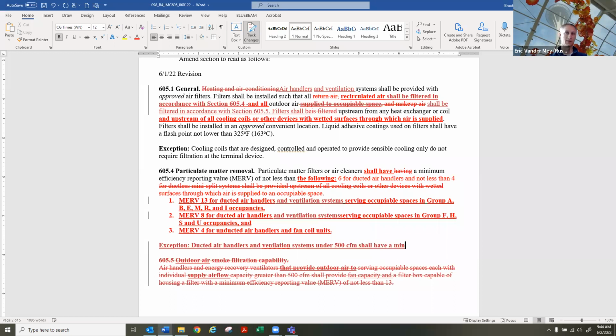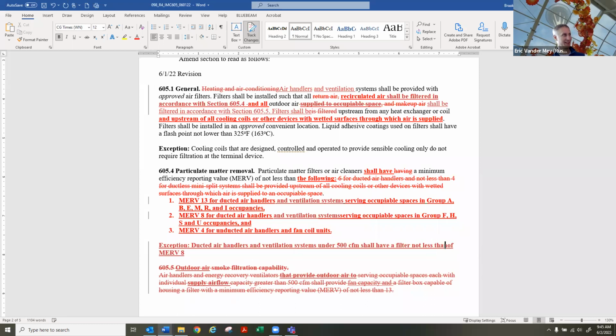Does it make sense to have this be an exception, or should it just be a number four that MERV 8 would be required for ducted air handlers and ventilation systems under 500 CFM? Because up above it says particulate matter air filters or air cleaners shall have a minimum efficiency reporting value of not less than the following. So instead of being an exception, you could just add it as MERV 8 as a requirement for ducted air handlers and ventilation systems under 500 CFM. I think it works better as an exception. Yeah, I think that would work, Chris, if items one and two said over 500 CFM, and then each of the items had an air threshold. I think this works.